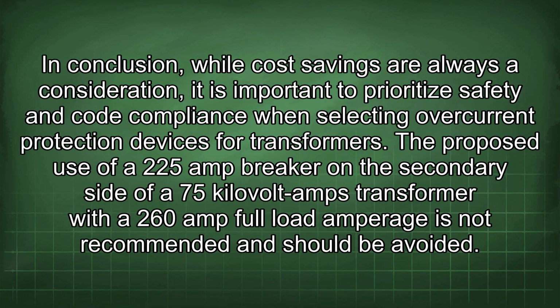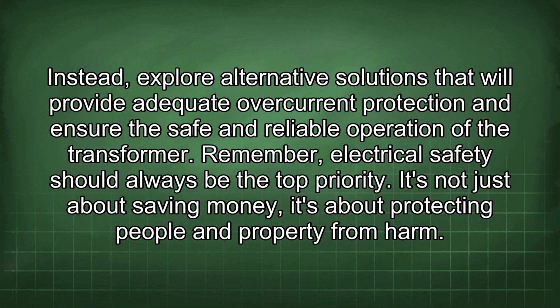In conclusion, while cost savings are always a consideration, it is important to prioritize safety and code compliance when selecting overcurrent protection devices for transformers. The proposed use of a 225 amp breaker on the secondary side of a 75 kilovolt-amps transformer with the 260 amp full load amperage is not recommended and should be avoided. Instead, explore alternative solutions that will provide adequate overcurrent protection and ensure the safe and reliable operation of the transformer.